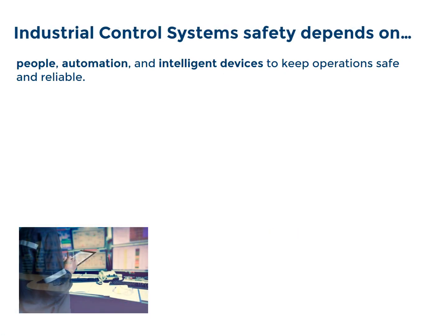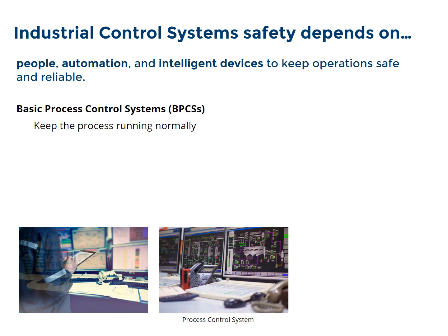Industrial control systems depend on people, automation, and intelligent devices to keep operations safe and reliable. The basic process control system, or BPCS, is the main computer system of the operating process. It receives information about the process — including pressure, temperature, flow, and level from transmitters — and transmits signals to manipulate control valves to ensure the system continues to operate under desired conditions. You can think of it like the human body: when you eat something, you don't think about how to digest it. Your body's basic process control system knows where to send the food and what chemicals to add, all within operational limits — unless you get indigestion.